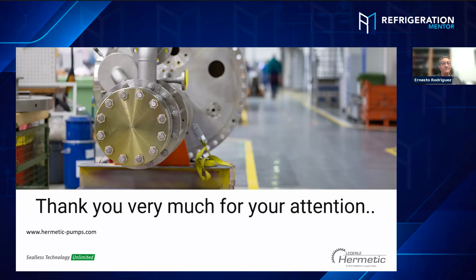The production says, hey, we don't have liquid in the coils, I am not able to reduce the temperature. What's happening? Go to the compressor, check the valve, but then not check the pump. When you overload the product, for example, the product is going to enter at 35, 40 Fahrenheit to the freezer. Okay, 40 Fahrenheit is a recommendation, or 36 Fahrenheit. But at some points it's 50, 55. I said, I don't care. Load it and close the door and run it.